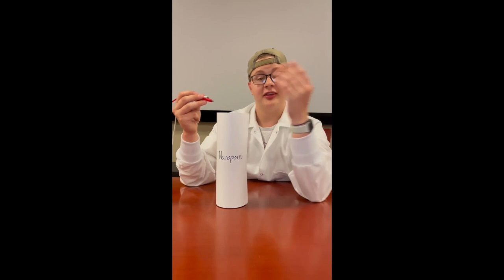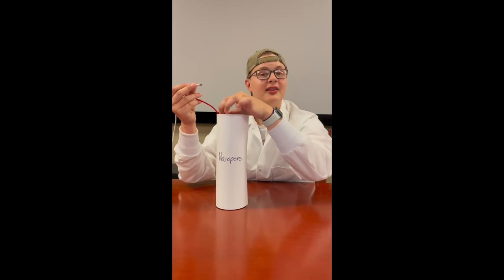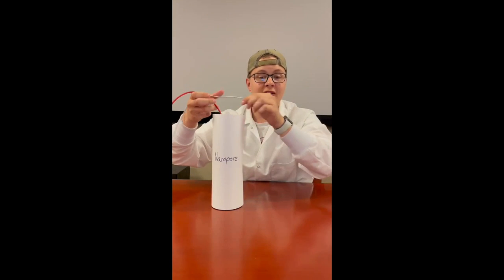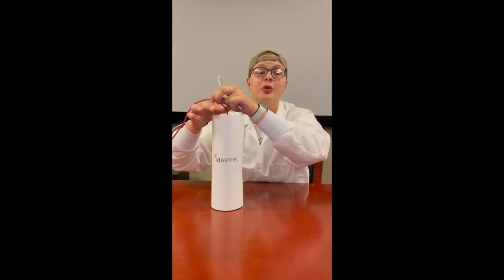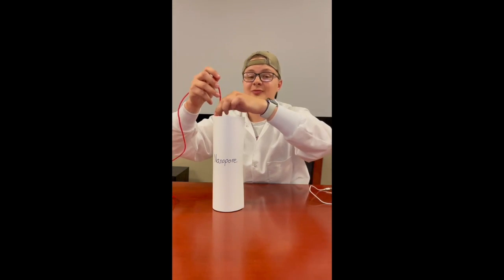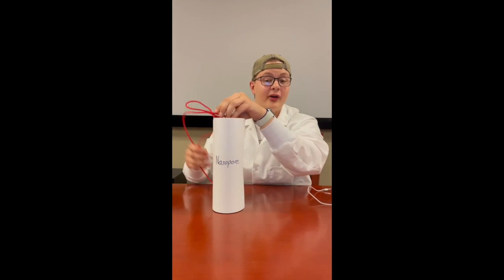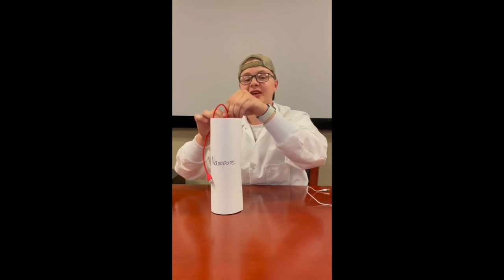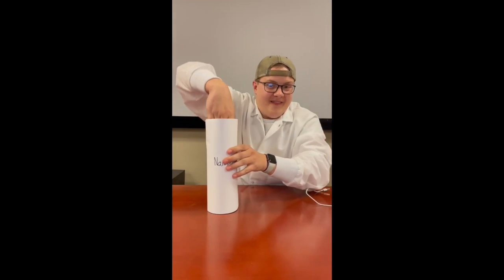But let's delve into how the nanopore sequencer does its science. The nanopores are within the membrane wells of the flow cell. A tether is then used to guide the DNA or RNA sample into the nanopore, which then uses current signals with different blocking degrees and blocking times to generate the sequence. This means that each nucleic acid molecule can be identified with its very own special current signal. The sequence is then formed and fed into the computer program's database.